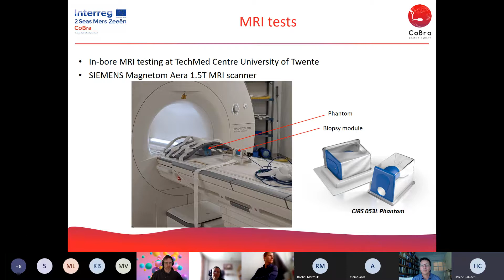Also the dots you can see over here, and there wasn't any distortion visible on the normal use of the system. So we didn't see any artifacts or distortions from the materials. Also the encoder signals were fine in both the static and the active MRI field. We had no problems with the motor actuation either. Only if we actively moved the motor, we saw a little bit of noise in the MRI image. And then only very limited artifacts from the biopsy needle. I think you can never really exclude any artifacts from the biopsy needle, so we thought it was quite good.